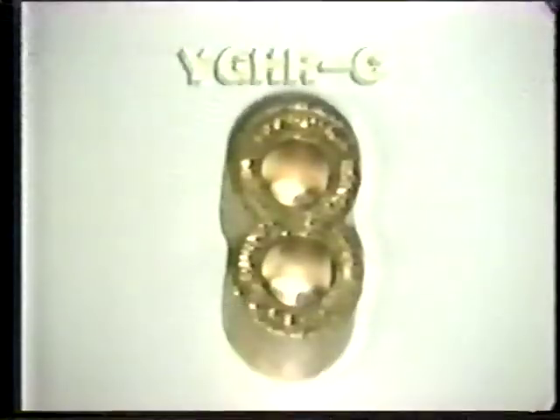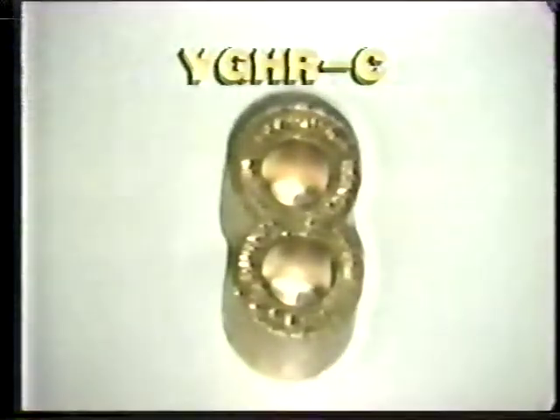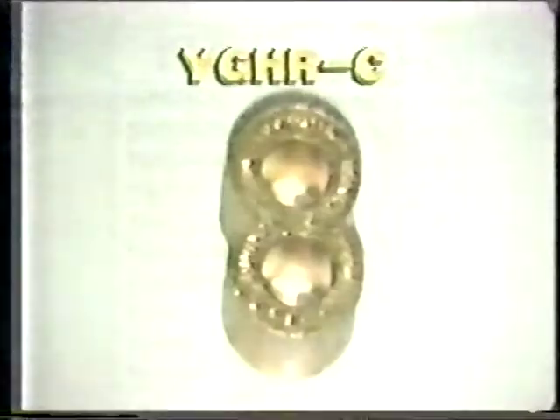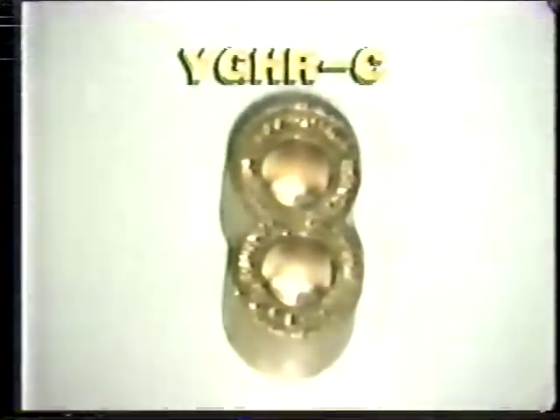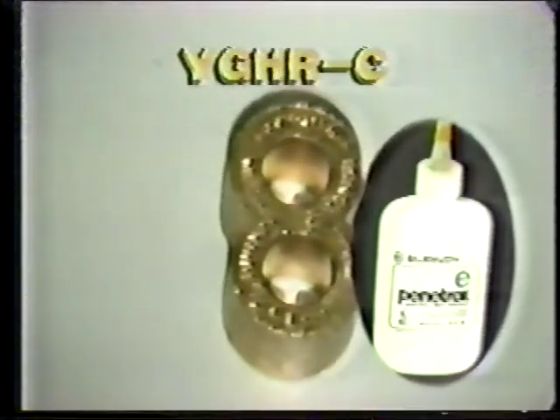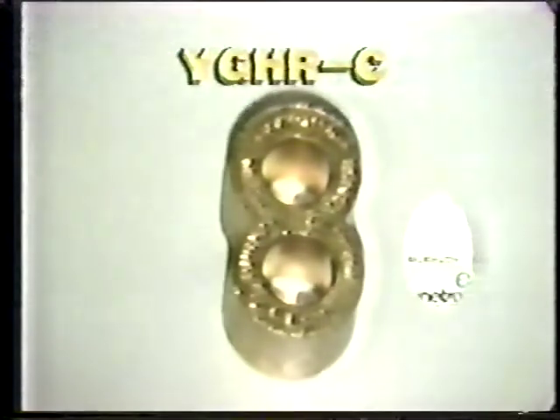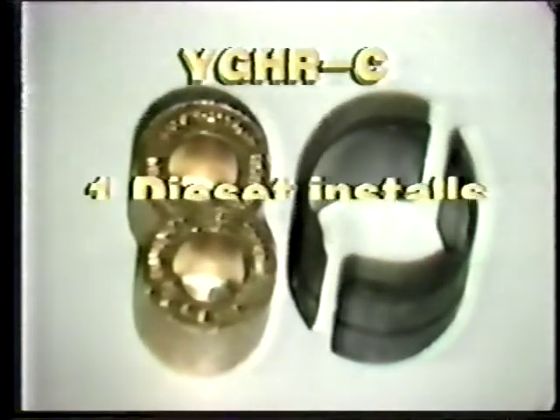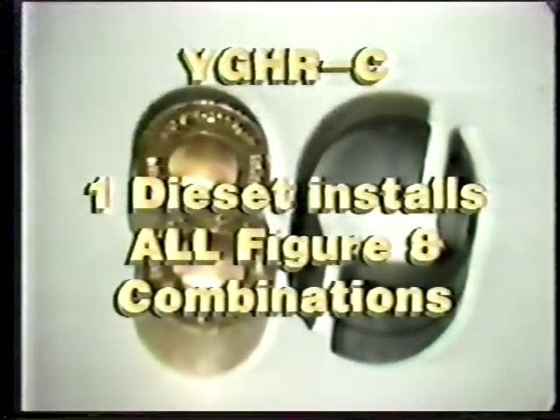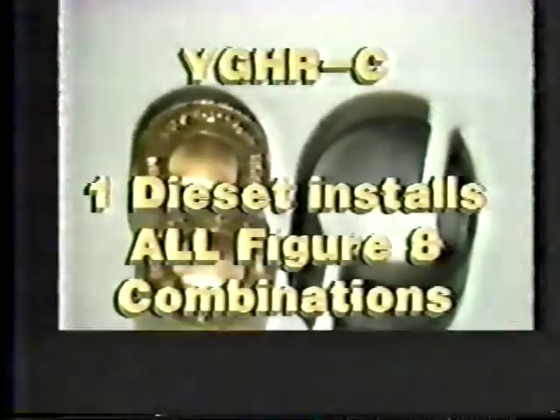Burndy offers a high-torque figure 8 ground rod dead-end connector accommodating a full range of rod diameters and conductors with only 10 range-taking connectors. These connectors are pre-filled with Burndy's Penetrox E compound and meet the latest UL and IEEE requirements. In addition, all figure 8 connector combinations can be installed with only 1 die set.